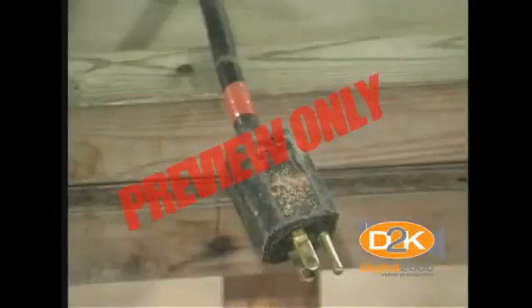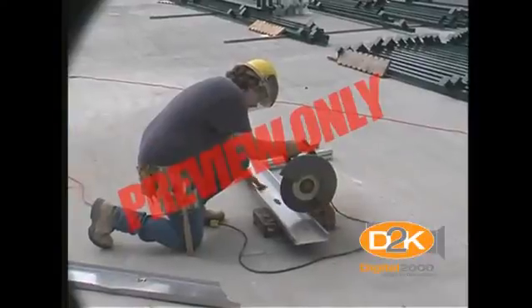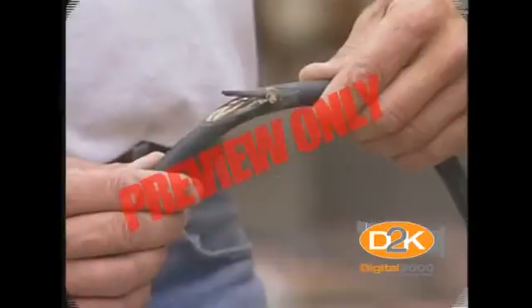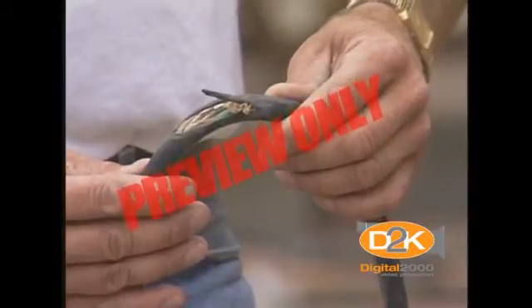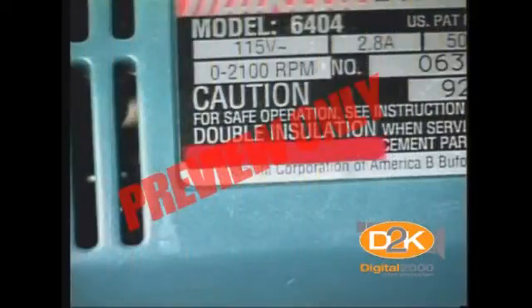There is one disadvantage to grounding. A break in the grounding system may occur without the user's knowledge. Insulation may be damaged by hard usage on the job or simply by aging. If this damage causes the conductors to become exposed, the hazards of shocks, burns, and fire will exist. Double insulation may be used as additional protection on the live parts of a tool, but double insulation does not provide protection against defective cords and plugs or against heavy moisture conditions.